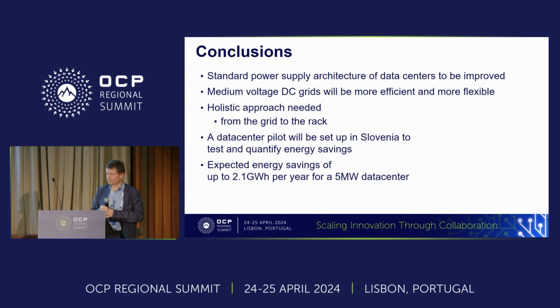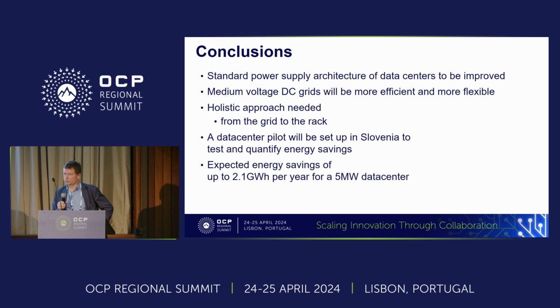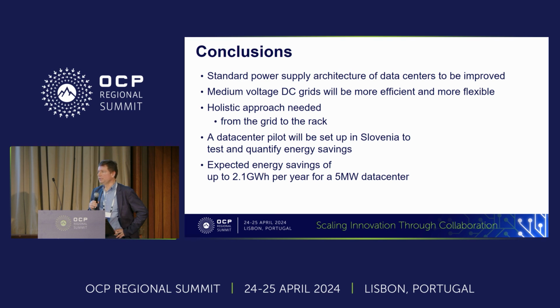So as a conclusion, the time is over, I hurry up. Well, standard power supply architecture of data centers is something which really needs to be improved, especially when we go to high power racks. Medium voltage DC grid is a more efficient and more flexible solution to do this. And actually, we need a holistic approach for powering data centers. So from the grid to the servers, the whole view is needed. So a data center will be set up as a pilot in Slovenia, and there is a lot of expected energy savings for this.